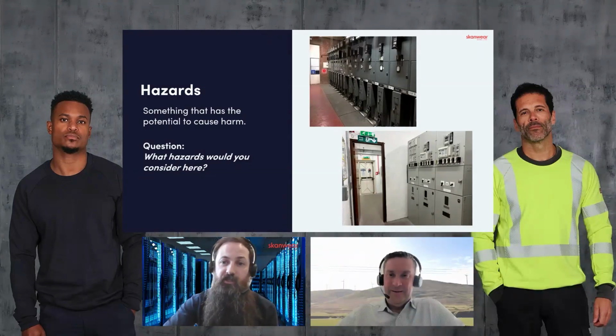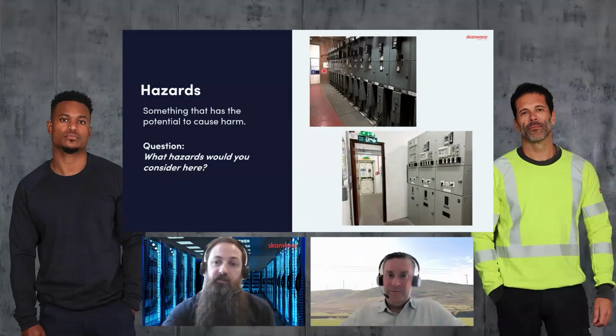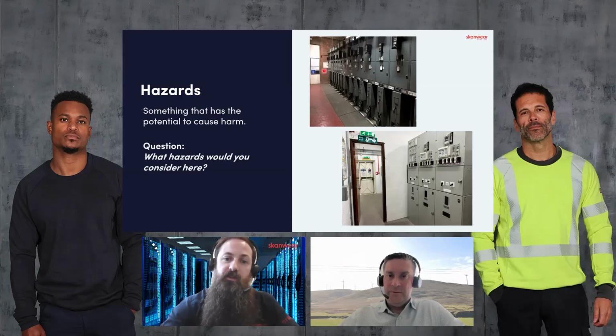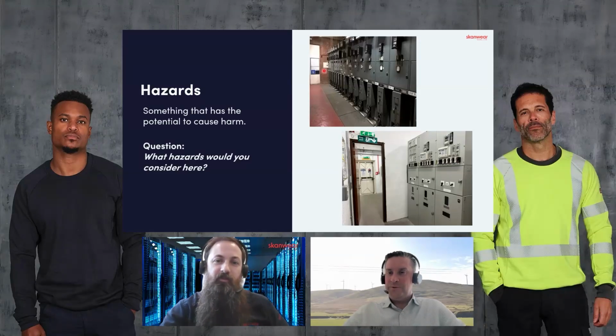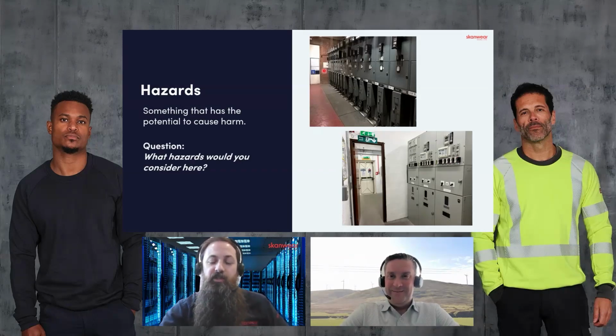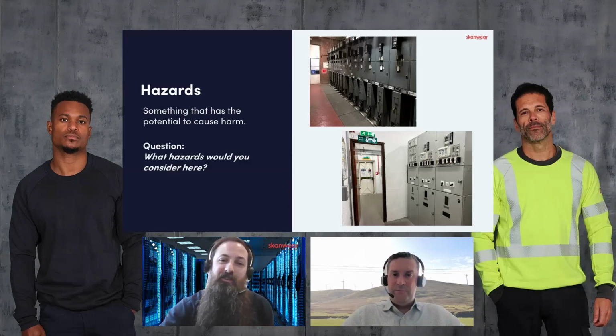What insulation medium - on this one, the top switchgear is oil insulated, so we've got an oil risk, bottom one's vacuum. Yep, arc flash, restricted access - you'll see there's no markings to indicate where the restricted access boundary is. Manual handling, racking in and out - sometimes they're not the easiest ergonomically, especially the old ones, though solid. Lighting, yeah - it's never at a premium especially in indoor spaces, like maybe one or two strip lights depending on the age of the substation, but it's never given a massive amount of attention, so it's definitely a hazard that can cause risk. Adjacent circuits, doors left open, rubber matting could be a trip hazard - it's there for a reason, but it could introduce another hazard into the workplace.